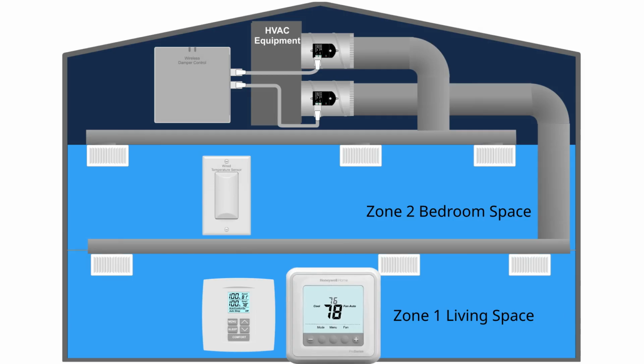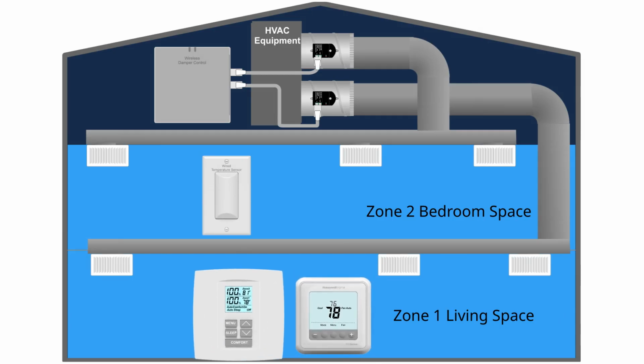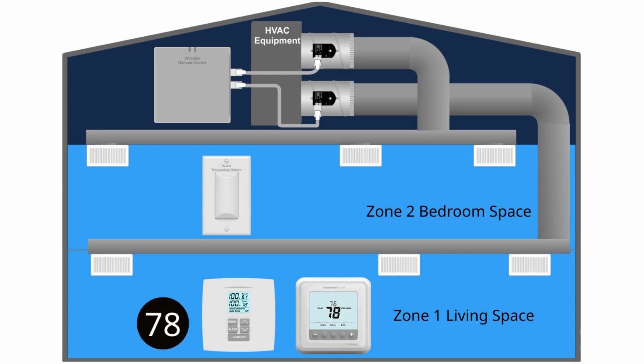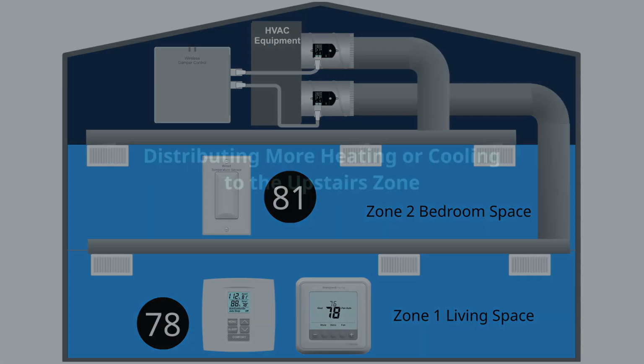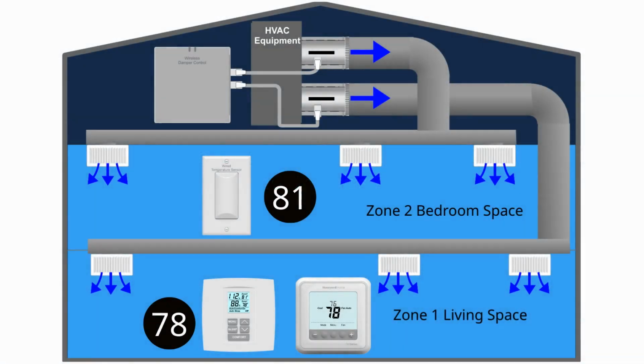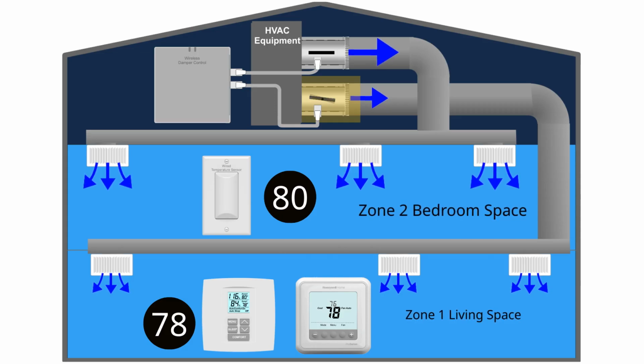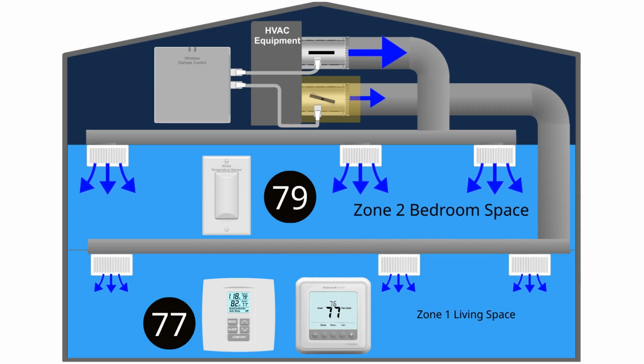The thermostat controls the equipment, while the two-zone comfort control monitors the equipment for heating and cooling calls and monitors the downstairs temperature at the control and the upstairs temperature at the sensor. If the upstairs and downstairs temperatures differ by 2 degrees or more, the two-zone control automatically distributes more heating or cooling to the zone that needs it. To distribute more heating or cooling upstairs, the upstairs damper fully opens and the downstairs damper closes 2% every 2 minutes, forcing more heating or cooling to the upstairs zone, improving comfort upstairs without overheating or overcooling the downstairs.